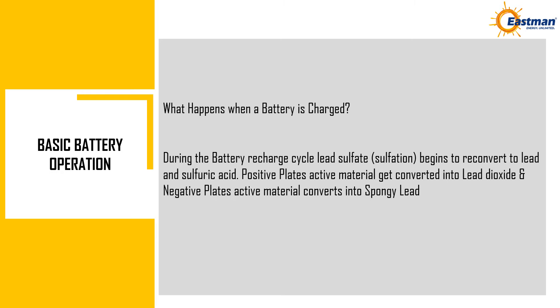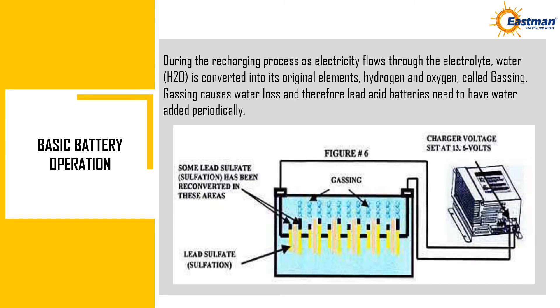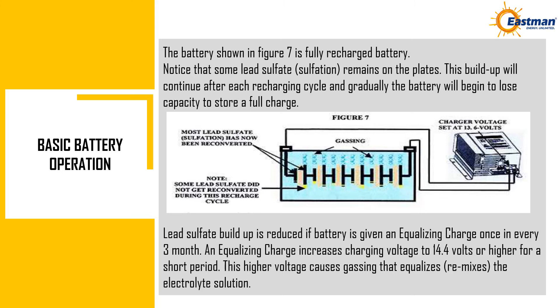What happens when a battery is charged? During the battery recharge cycle, lead sulfate (sulfation) begins to reconvert to lead and sulfuric acid. Positive plates' active material is converted into lead dioxide and negative plates' active material converts into spongy lead. During the recharging process, as electricity flows through the electrolyte, water (H₂O) is converted into its original elements — hydrogen and oxygen — called gassing. Gassing causes water loss, and therefore lead acid batteries need to have water added periodically. The battery shown in FIG 7 is a fully recharged battery.